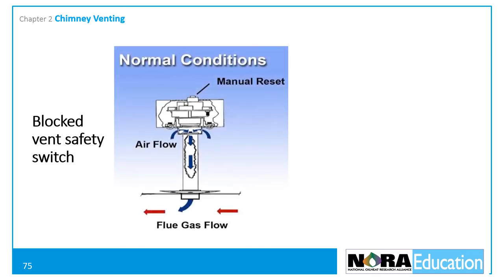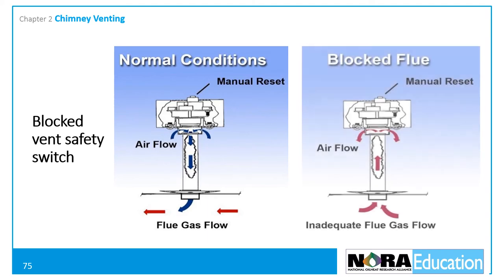In the first illustration, flue gases flow from right to left and draft is sufficient to pull air through openings in the switch housing assembly, keeping the sensor at ambient room temperature. In the second illustration, flue gases are not flowing through to the chimney and are pushing up against the sensor. In this situation, the sensor will overheat and power to the burner will be shut off.